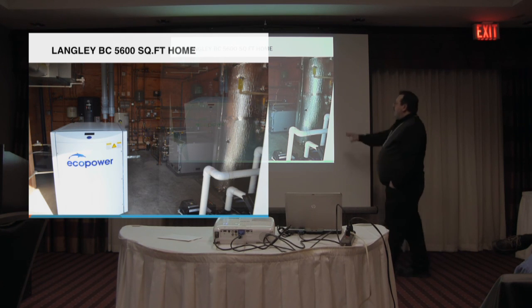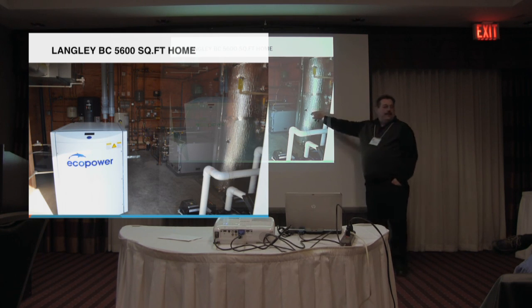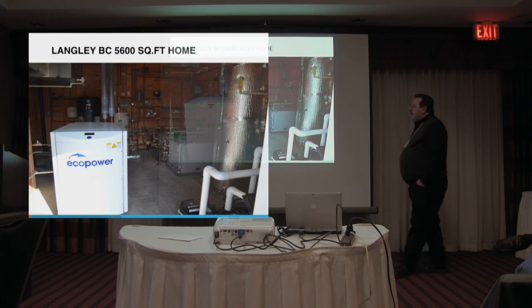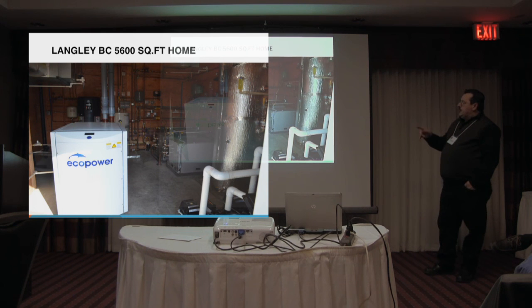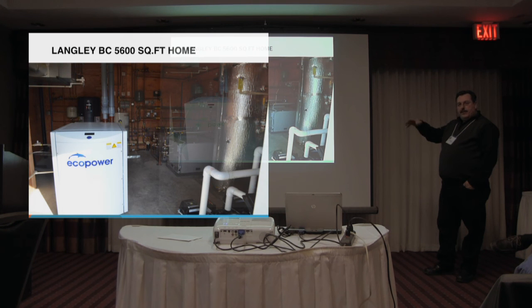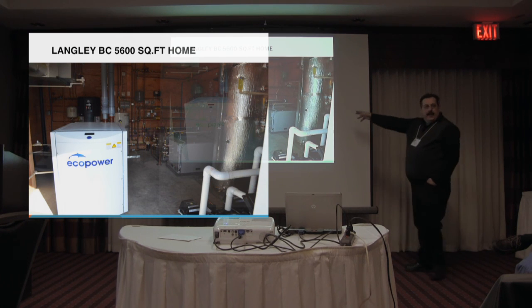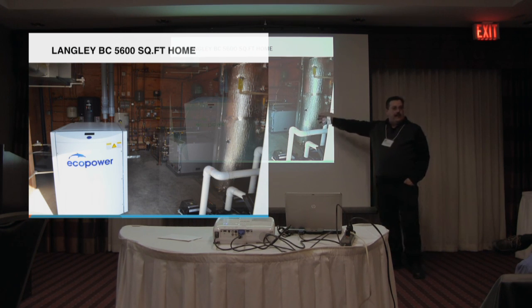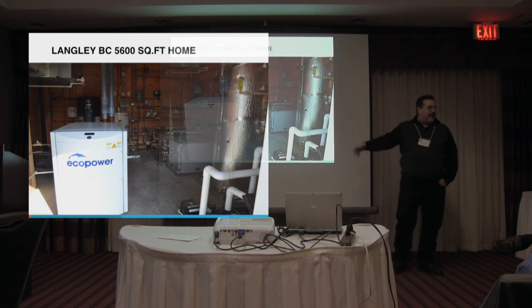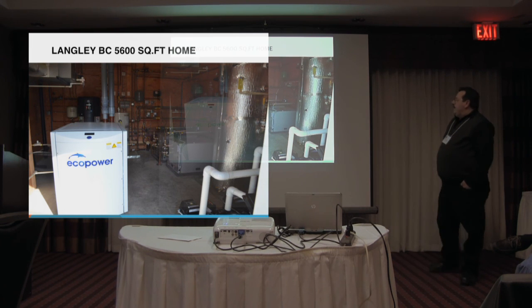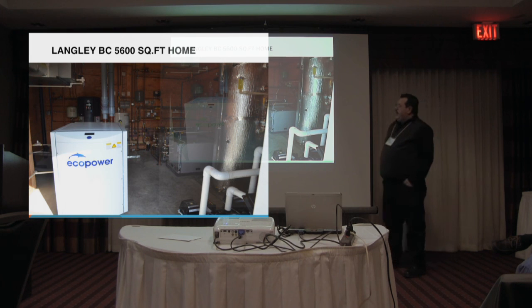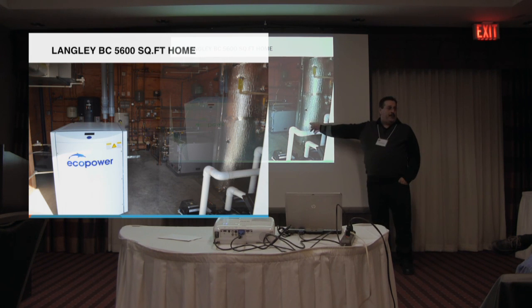And everything is coupled to this buffer tank. This is a 250-gallon ASME rated tank here that's wrapped. And the way the system is controlled is that we know the CHP, assuming that there's not a lot of load on it, we can get the temperature in this tank up to 167 degrees Fahrenheit. And we know that the geothermal units will never accept that water temperature. You couldn't run them if you wanted to. They would just go off on a high head right away. So the geothermal units don't kick in until this tank temperature drops down to 110 degrees.